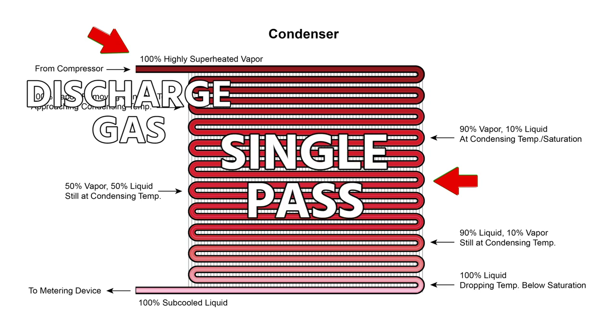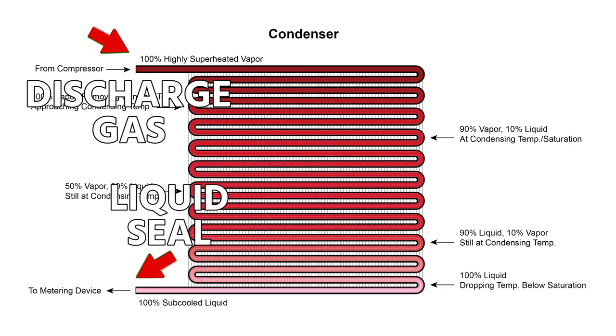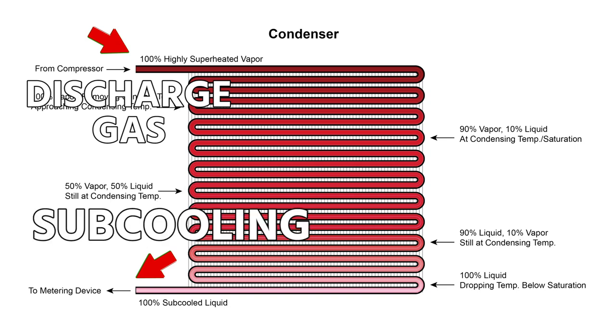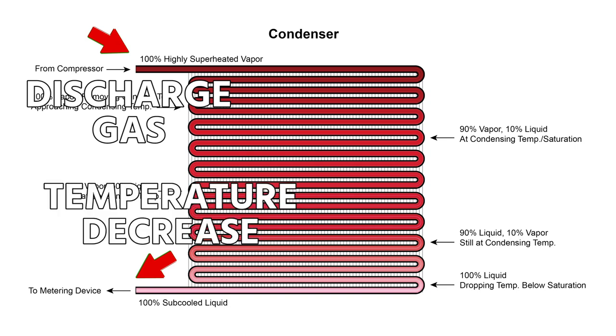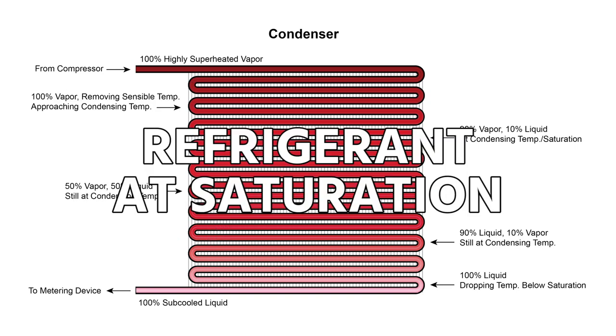In this image it shows a single pass. Condensers are generally multiple passes with headers, but it creates a liquid seal down at the bottom once it fully condenses. And that's where we see subcooling, because subcooling is the temperature decrease in refrigerant once it goes below that condensing temperature, or what we call our liquid saturation temperature.